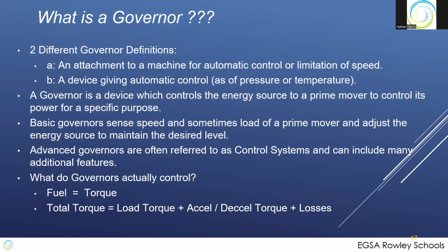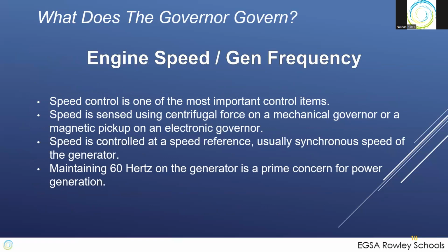And I say it that way carefully because if it's a single gen, single load, increase fuel, you'll increase speed. Single gen, parallel with utility, increase fuel, increase torque, which increases the kW output. So the governor, although it's affected by kW, is actually controlling the fuel, which is actually torque, not speed, not watts necessarily, it's torque. So the governor controls the speed during single generator, single load configurations.